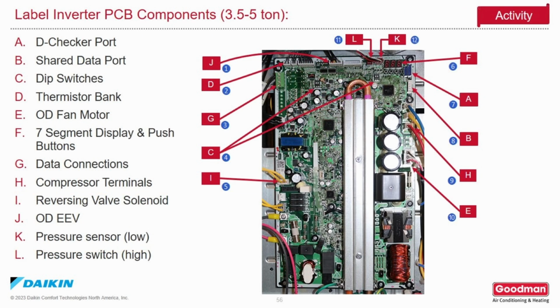Here is a list and locations of the inverter PC board components on a 3.5 to 5 ton. D-checker port, shared data port, dip switches, thermistor bank, outdoor fan motor, the 7-segment display and the push buttons, data connections, compressor terminals, reversing valve solenoid, outdoor EEV, low pressure sensor, high pressure switch.